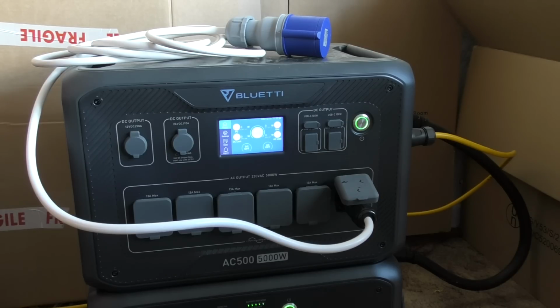The problem is that you need to arrange it so that it's not possible to have the output connected while your grid connection is still there, primarily because it's probably going to blow the output apart if this thing sees mains on its output. And obviously you also don't want to be powering the rest of your neighbourhood. In areas like the US this is talked about quite a lot, where it's not uncommon for a house to be on the end of a single high voltage transformer, so backfeeding into that could put high voltage on the line, which could be hazardous. In the UK that's less of a problem. It's just that you're connected to the rest of your neighbourhood, so it's just not going to work.